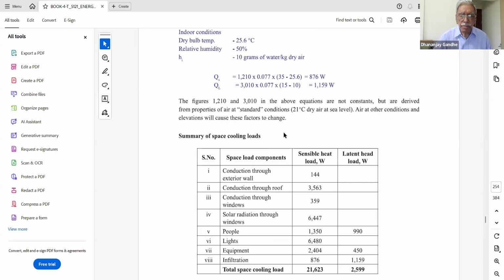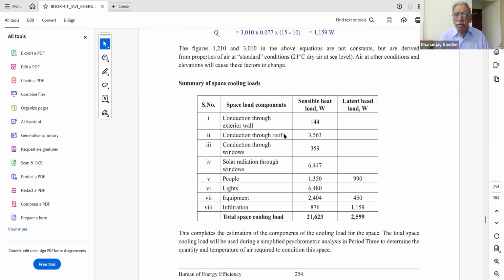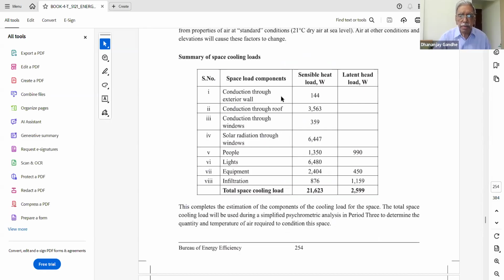So with all calculations done, this is a summary of the space cooling loads, or the heat loads on that particular space. This summary table tells you the space load components. The first is conduction through exterior walls. The sensible figure worked out earlier was 144. This is the same example carried forward. Conduction through roof was 3560. This figure also appears earlier. Conduction through windows, the value was 359, which was also worked out earlier. Radiation through windows is 6,447. That is also worked out earlier.